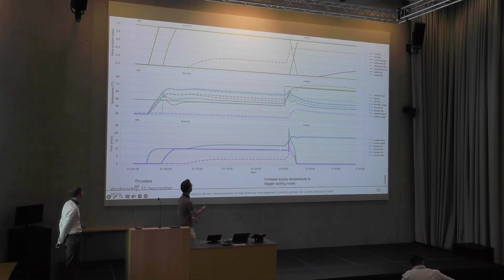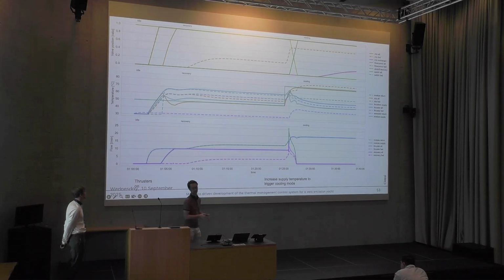As we go on, we reach this point where we ramp the supply temperature from 50 to 80 degrees, which means that the thruster is going to overshoot its set point, so it needs to switch from recovery to cooling, which it does. The valves switch directions so that the flow goes through the heat exchanger with the seawater, and then the temperature starts to drop.